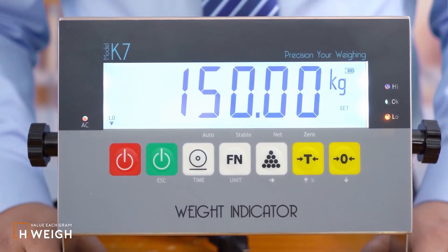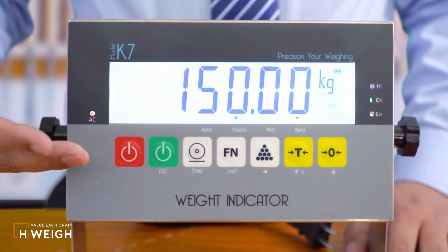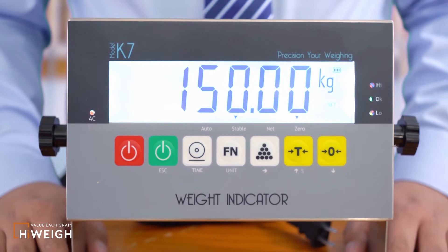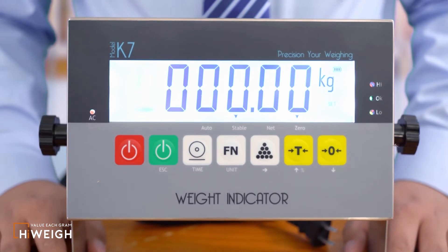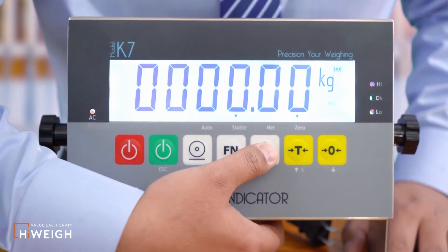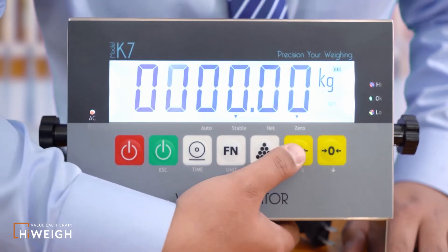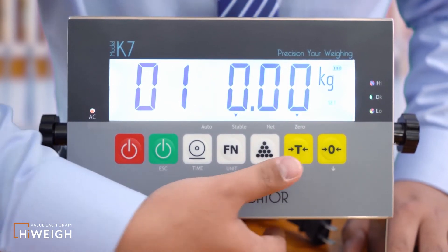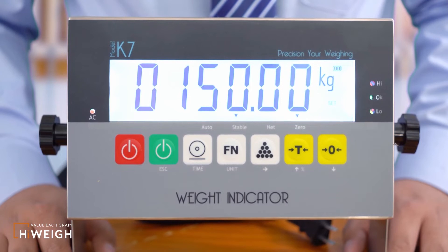The next is the configuration of the capacity for this division value. What appears is the capacity that has been saved. If you want to modify it, press the accumulation button to enter the modification interface — it will display zero. Press the accumulation button to shift digits, and press the tare button or the zero button to adjust the value of each digit to enter the capacity you want. Press the function button to save.